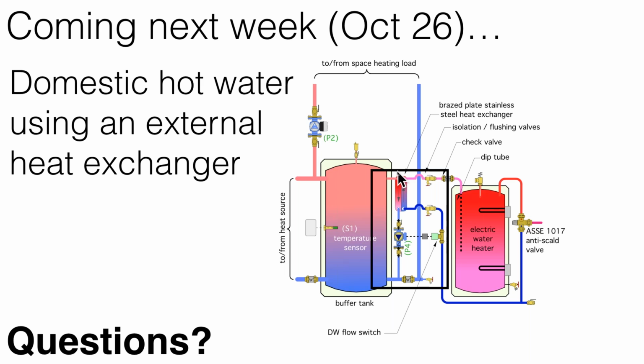What we wanted to avoid is adding more mixing valves. You could say, we could look at running 120-degree water to the panel rads and then adding a mixing valve and going down to, say, 105 on the floor. Quite honestly, we try to avoid that extra hardware. So what we did is we simply put everything in, and we looked at supply water temperatures and found that they were close enough that we just piped them in parallel.